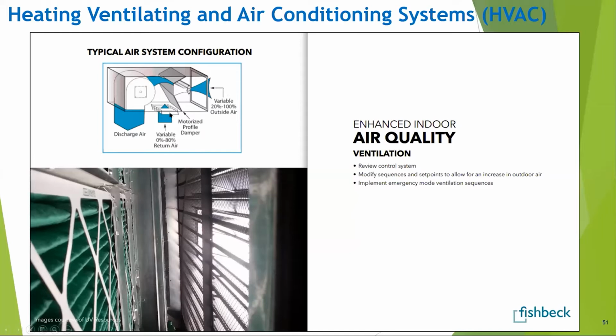then you do have some return air from the space. That's due to it's very difficult to 100% bring in outside air under a lot of conditions because you have so much energy input that you need to provide. So you often will mix outside and inside air, and there's a mechanism called a damper, which allows you to provide more or less outside fresh air depending on what type of a mode you're trying to run in. Those air streams mix, and then they're discharged into the occupied space.